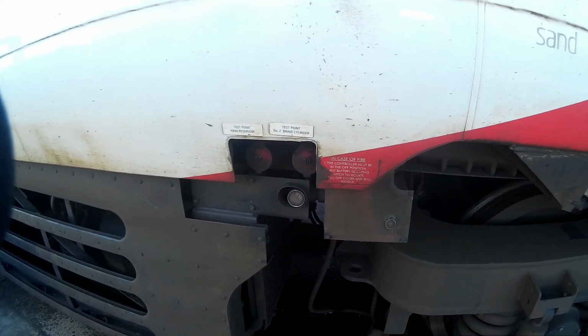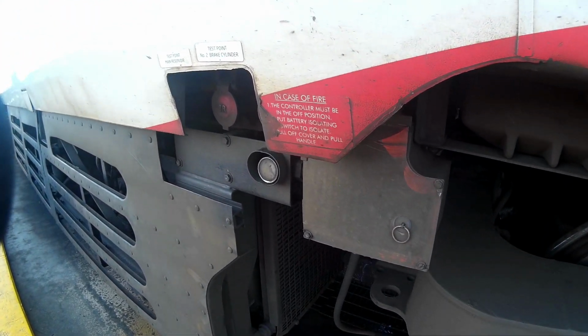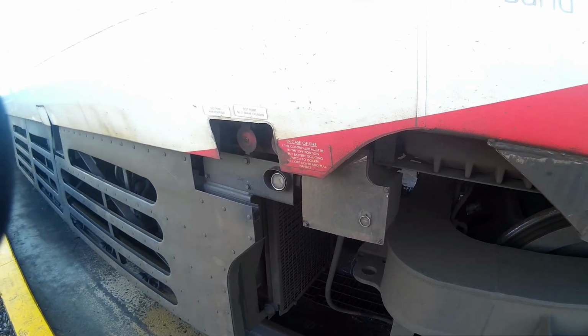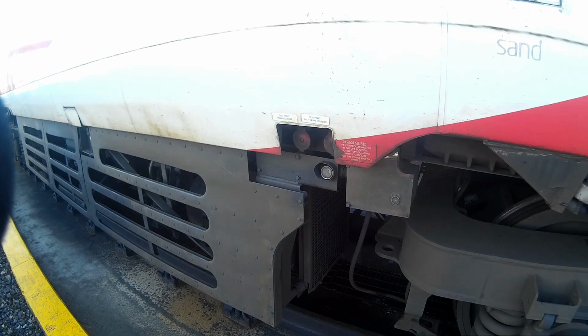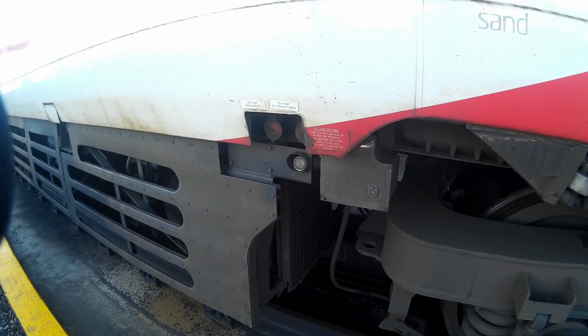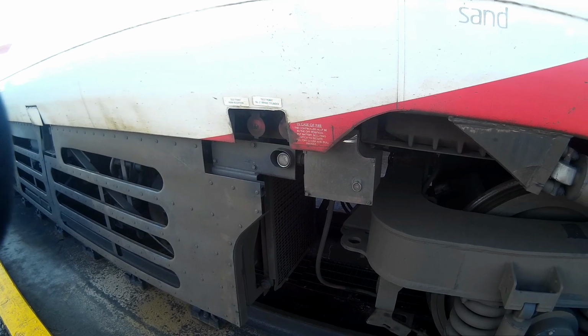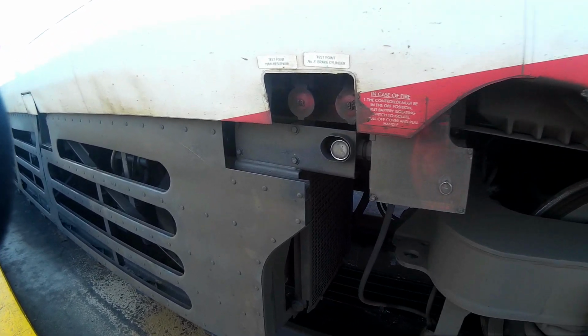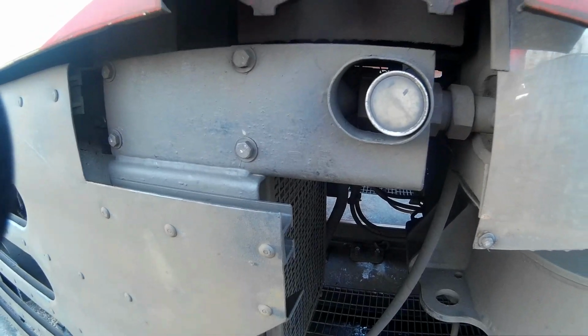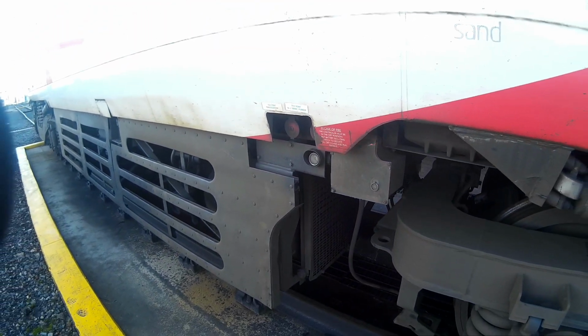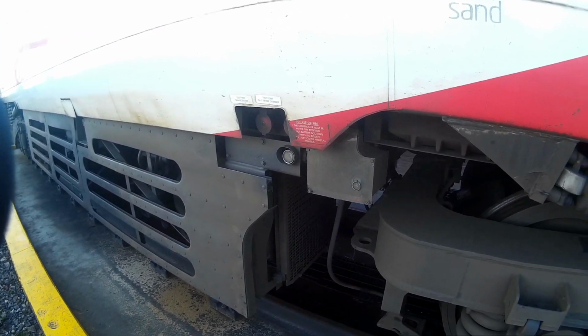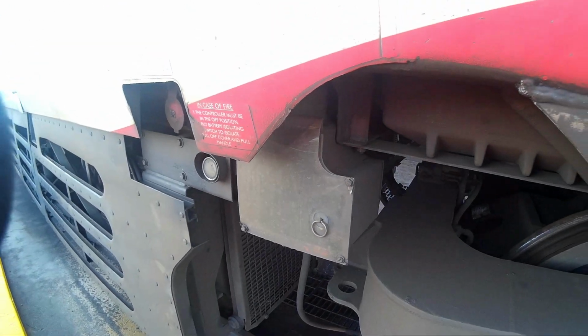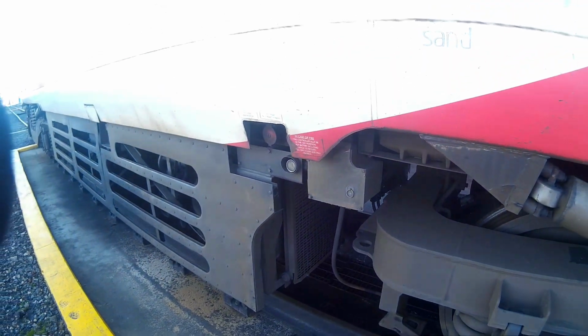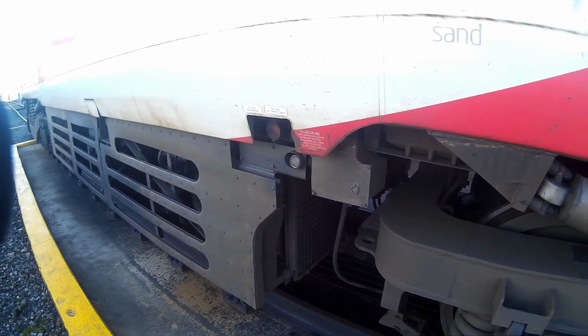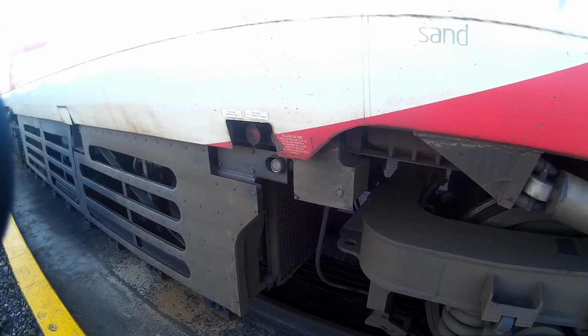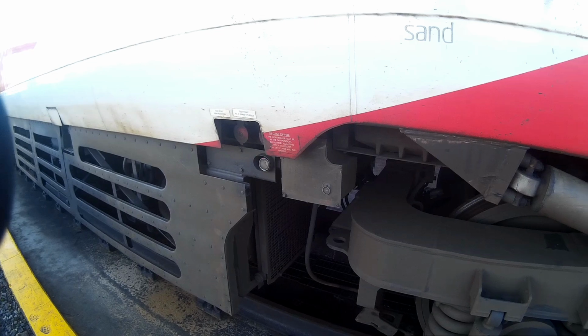We also have fixed firefighting equipment on the locomotive which we can manually operate. These consist of nitrogen bottles - one in each driving cab at the bulkhead, and one on each side of the locomotive just behind number 2 bogie. These have a nominal pressure of 50 bar; if it's any lower, the system won't operate. If that little flap is pulled and a lever inside is operated, it sends nitrogen pressure to the argonite bottles inside the locomotive, which then discharge into the engine room.